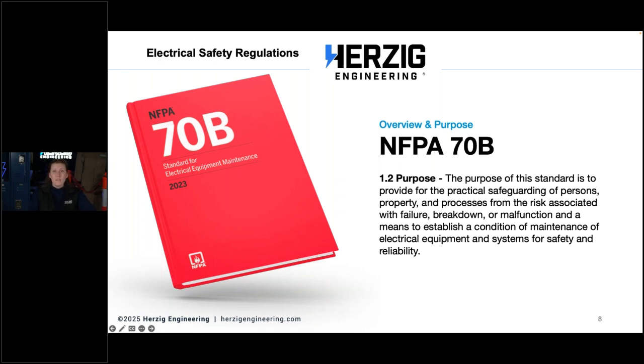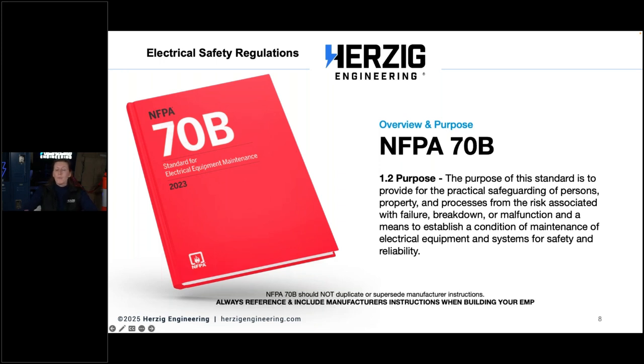So the 70B gives you the tools and methods to establish that baseline and figure out how to lower that risk. One thing to note: the NFPA 70B is not meant to duplicate or supersede manufacturer's instructions. If you already have a maintenance plan based on manufacturer requirements, this can help fill in any gaps, but you're not starting from scratch — it's meant to be used in conjunction with your manufacturer requirements for each specific piece of equipment.